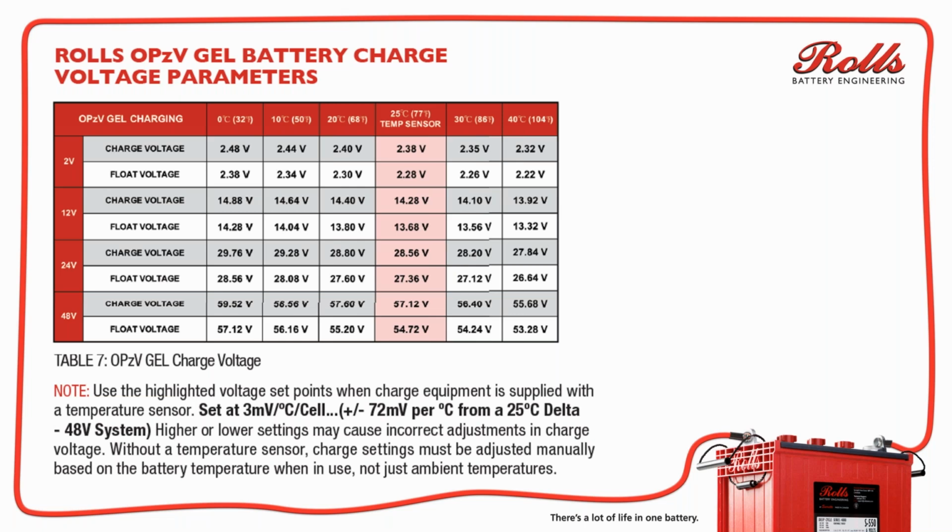Do the new higher charging voltages apply to old installed battery banks as well, i.e. someone has a 10-year-old battery bank? Yes and no. I would probably go halfway in between. It just depends on their current battery performance. It's all based on specific gravities. If the specific gravities are all good, leave it alone. If the specific gravities are bad or low, or they're struggling to get the specific gravities up into that 1260 to 1275 range, then you might want to slowly bump up your voltages.